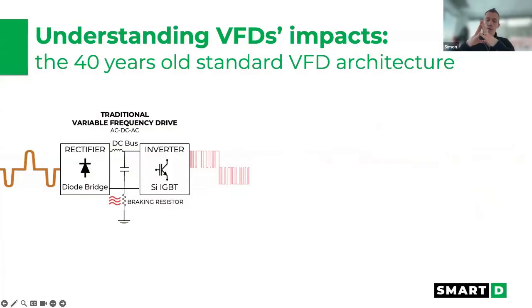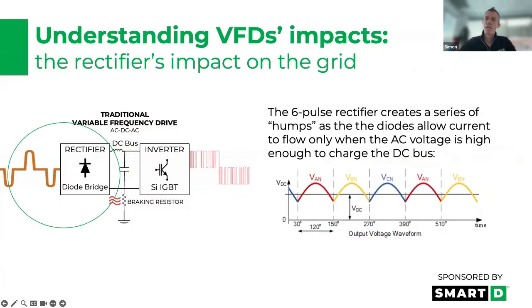Harmonics, to understand where they come from in a VFD, we just need to remind ourselves of the VFD architecture. Three parts to the VFD: the diode bridge rectifier, the DC bus, and the inverter. In the case of grid side harmonics, they're mainly caused by the diode bridge, which is letting current through only when the voltage is high enough to charge the DC bus. This means that in between these little humps, you have 0 current draw. And so you're having a nonlinear draw on the grid, and that is the core source of your harmonics.